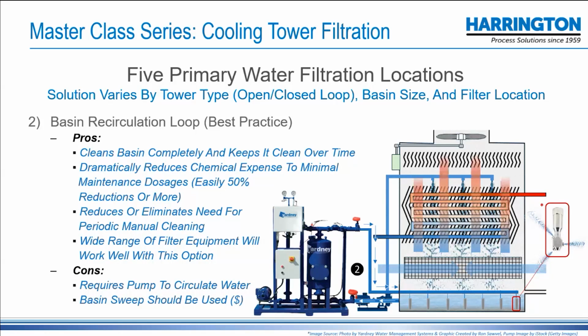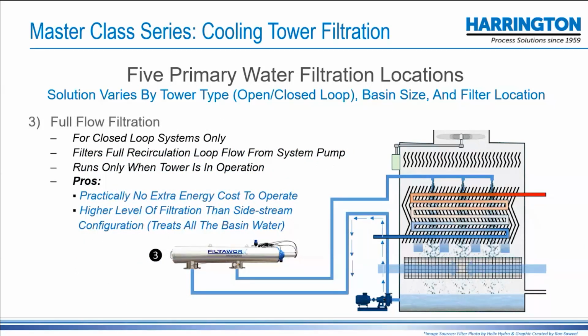And if you do that, you're not only going to eliminate sludge and for the most part debris in the basin water, you'll keep your spray nozzles and dispersal elements and equipment pristinely clean without having to crawl into the basin with a bucket and a shovel and clean it out periodically. And most likely you're going to see a reduction, I'll say, of 75% of your chemical usage. And remember, at least for the mix that semiconductor plant was buying, they're $20,000 a tote. It's a huge savings. And so we'll talk about some of the individual equipment as we go along.